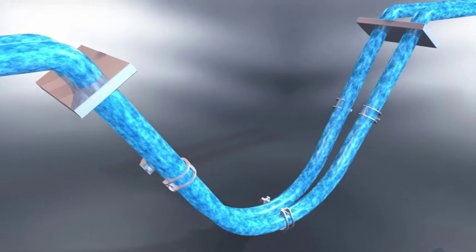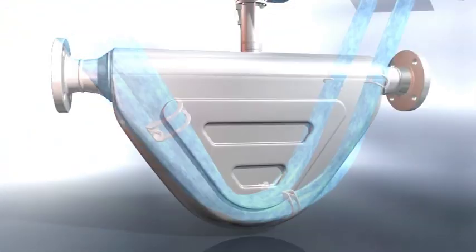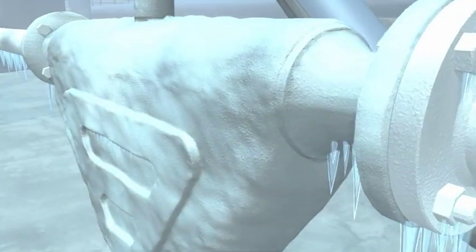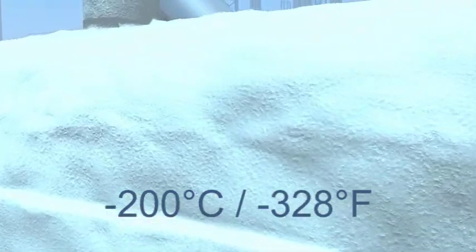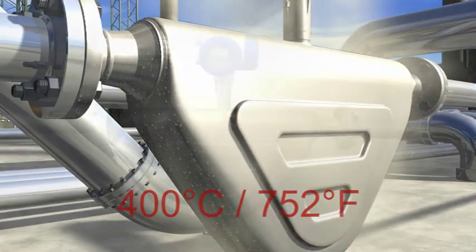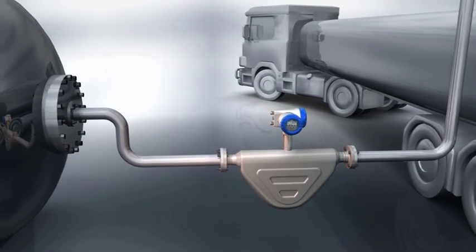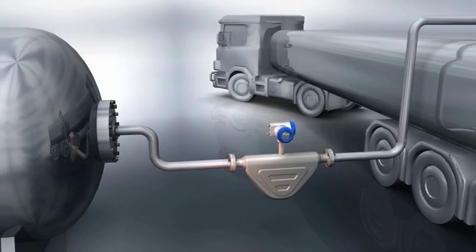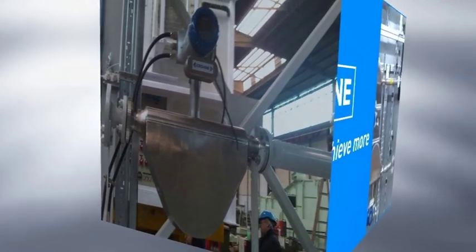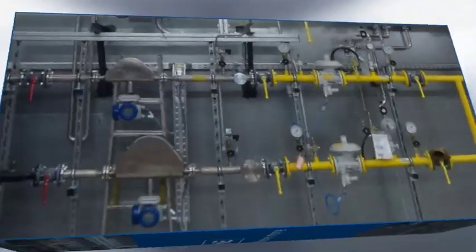Krohne's OptiMass 6400 is a twin-bent tube design for process industries that demand high performance as standard. It can operate down to cryogenic temperatures as low as minus 200 degrees centigrade and up to high temperatures of 400 degrees centigrade. The 6400 is capable of both liquid and gas custody transfer according to OIML and MID, and complies with API and AGA guidelines. The OptiMass 6400 has grown from decades of mass flow expertise and direct industry experience.